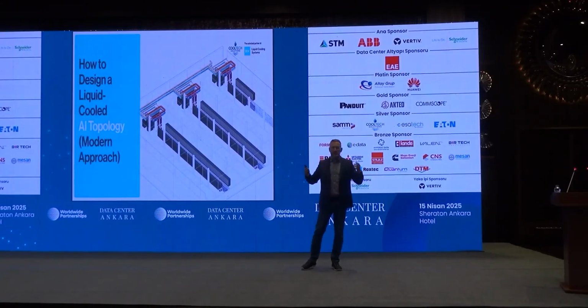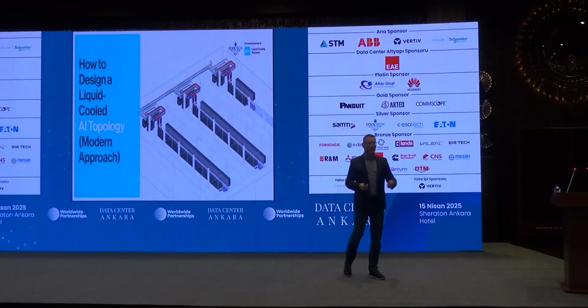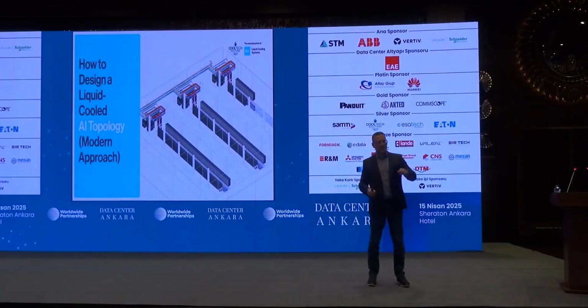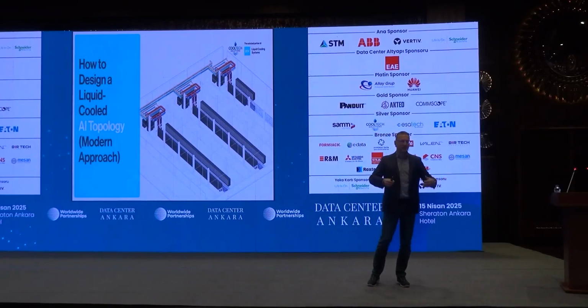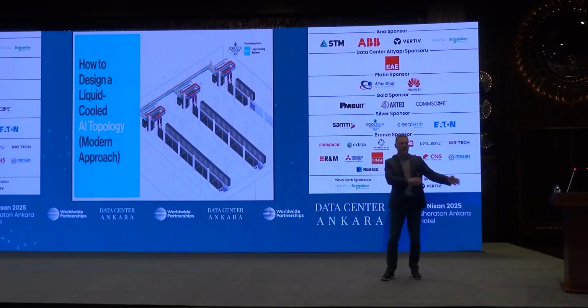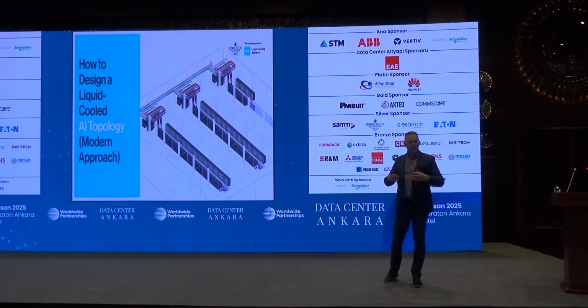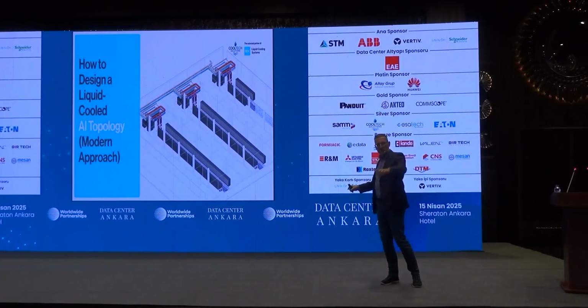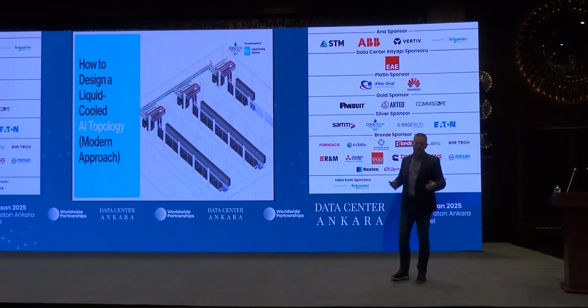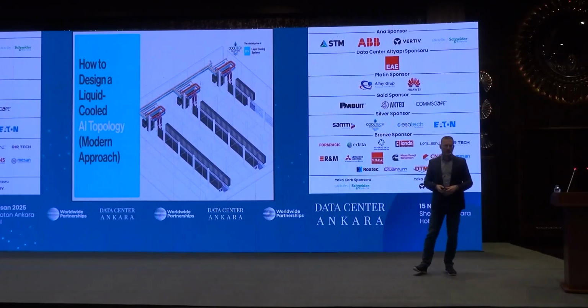Let's separate mechanically the power and compute, busway, bus bars, containment, everything, from the hydraulic systems. Because hydraulic systems mean messy - reservoirs, adding coolants, changing coolants, replacing filters, eventually replacing pump motors. So you don't want to do that on the white space. Ideally, let's put those - the rows can be shorter or longer, that doesn't matter - but let's put the loops, all those CDUs, all that messy part, all those pumps, in a separate room. It could be a technical corridor.